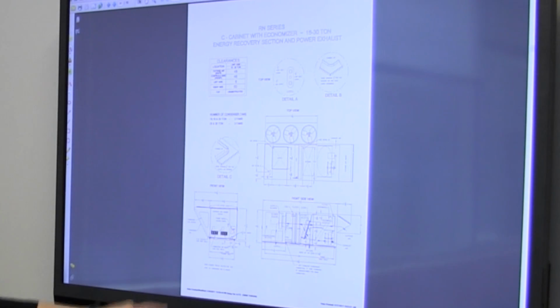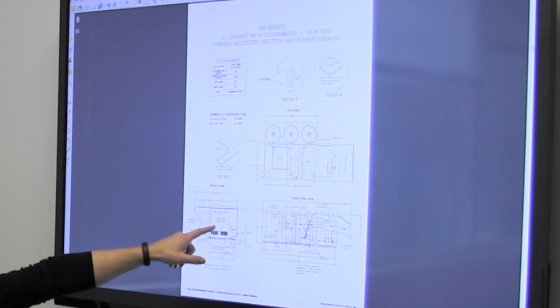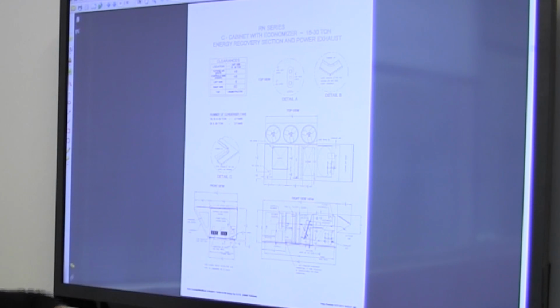And then the control cabinet on the end has a whole lot more in it than with those other units. Instead of the water coil that could do hot water or chilled water, this is a DX coil, and it can heat or cool because it's a heat pump. There's a defrost controller in each unit. When that defrost controller activates, it then turns on the electric heat so that it can give neutral air while it's in defrost mode.